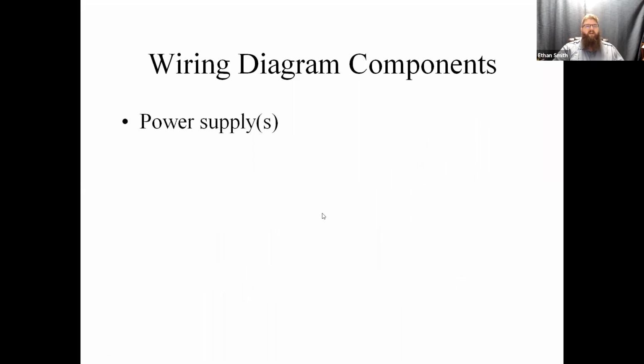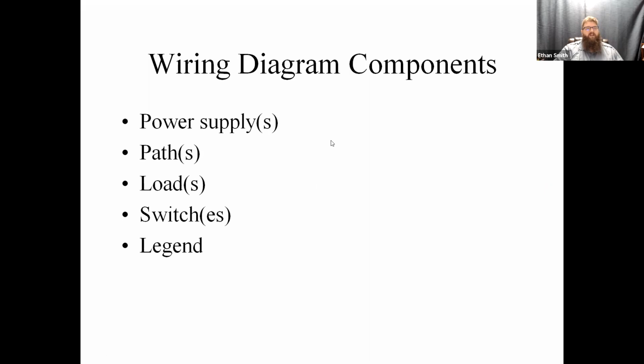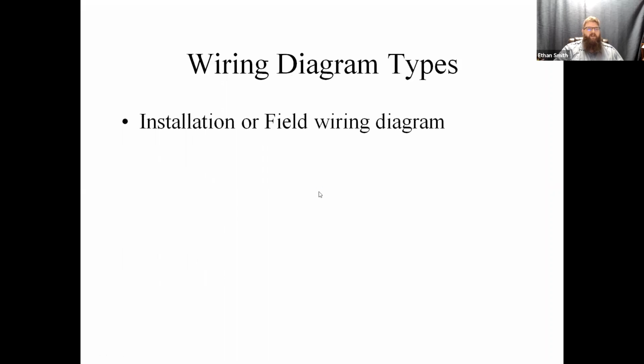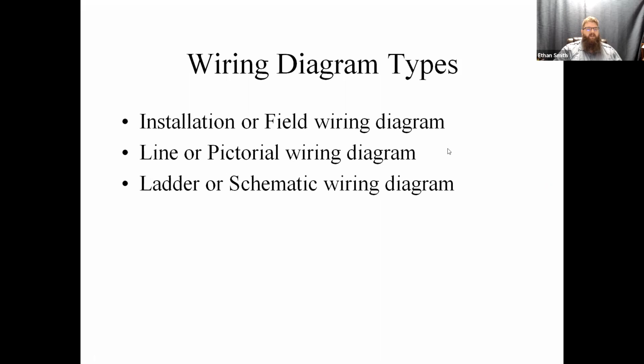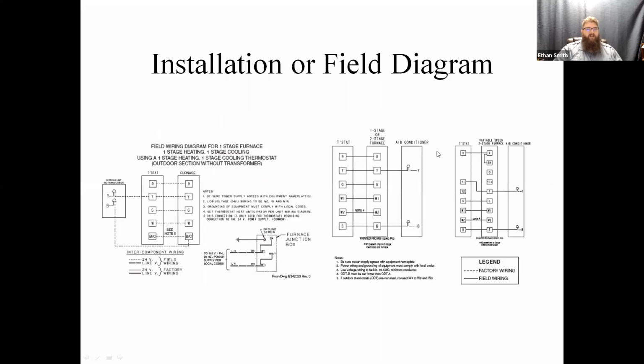Okay. So any wiring diagram is going to have a power supply. It's going to have some type of path that it shows. You're going to have your loads. You're going to have your controls or your switches. And usually there's something that tells you what everything means. So it'll have symbols. If your wiring diagram is really good, you might have a locator system built into it. So we've got lots of different wiring diagrams out there. Some of them are simplified for installation or field wiring. We've got line or pictorial wiring diagrams. We looked at that pictorial a minute ago. Ladder or schematics. And they're all useful for different things.